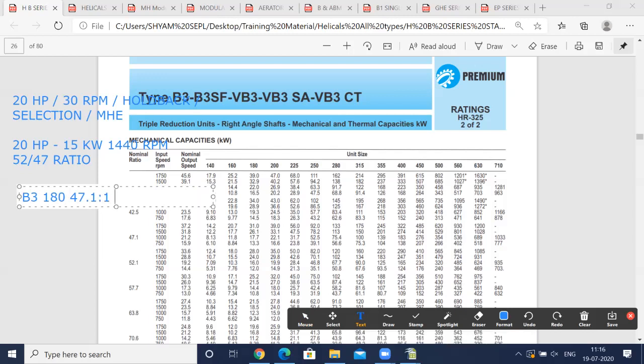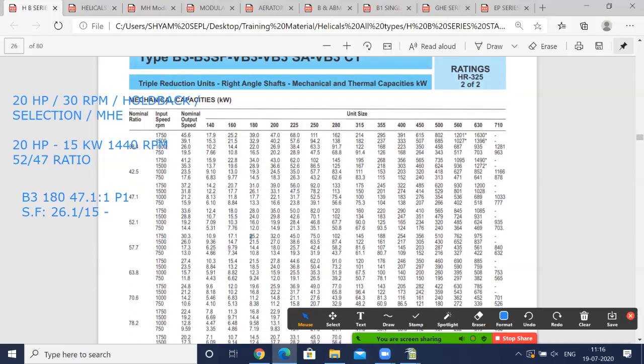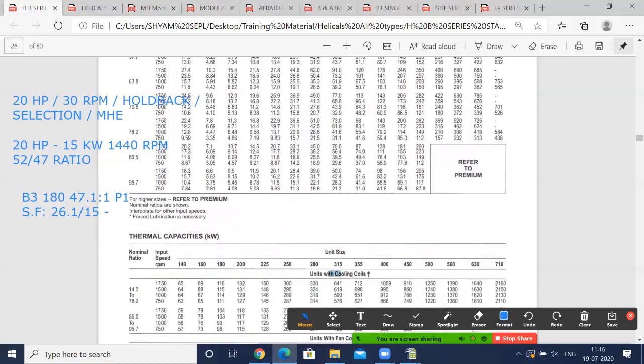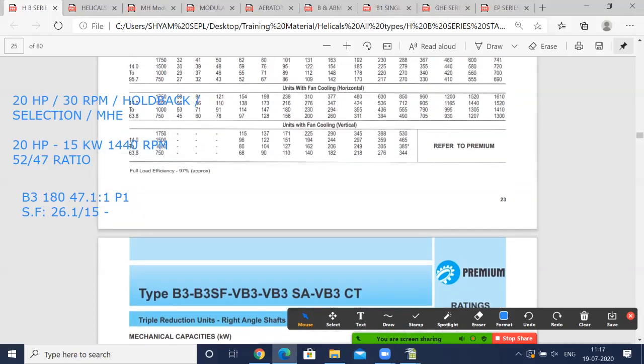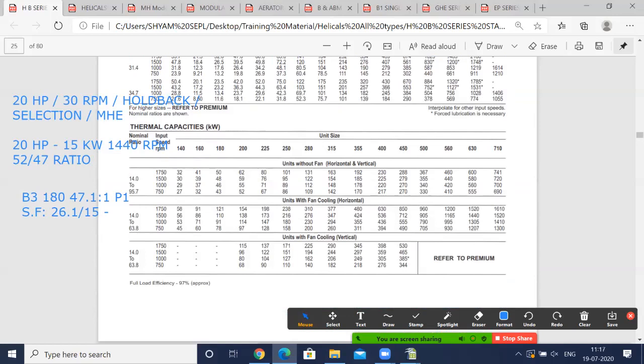Position P1 or P1A, P2 or P2A. Okay, suppose P1. Now the safety factor will be 26.1 divided by 15. That will give you the safety factor. Thermal capacity, let's check thermal capacity. Thermal capacity is with cooling coil. No, we need to go to the next page, back page, so we can check the thermal. Yeah. So thermal capacity from ratio 14 to 95 for without fan for 180 is 48 kilowatt. So it is much within limit. Ours is just 15 kilowatt, it is 48.